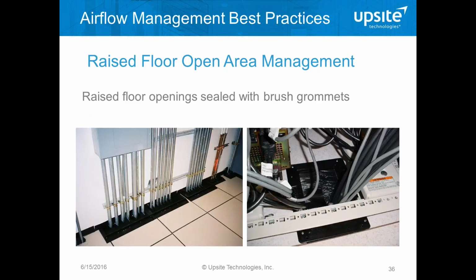Then, as we have here on the slide, raised floor open area management is the next really important area to pay attention to. Very few people have quantified what percentage of openings in the raised floor are in a good location, and the only way that you have an opening in a good location is a supply tile in front of IT equipment. And all other openings, cable openings behind cabinets or perimeter penetrations, or as we see in these pictures, picture on the left, conduits running along the walls, every one of these openings is a bad opening. And all of them should be sealed. And it's surprising how much open area this represents when you go look at it and add it up.